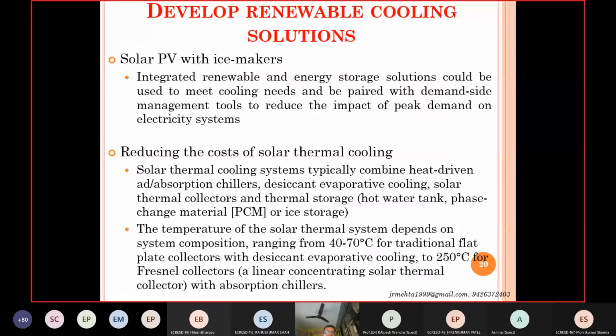Then develop renewable cooling solutions. Renewable energy sources like solar photovoltaic, and storage in the form of ice makers. So you can make ice during off-peak hours and utilize it during the peak hours, and reduce the cost of solar thermal cooling. So storage is also an important part, as is adopting certain technologies which have lower demand for electrical power. And the temperature of the solar thermal system depends on the system composition, ranging from 40 to 70 for flat plate collector with desiccant evaporative cooling, and to 250 degrees Celsius for Fresnel lens based absorption chiller. So there are different technologies, and the firing temperatures are different for different technologies. We'll see that in detail later.